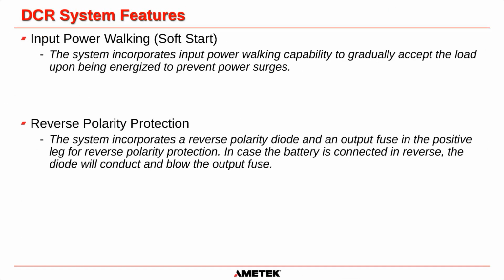Some features of our DCR system. We have input power walking, so we slowly, gradually ramp up the DC voltage and current to accept the load and prevent power surges. And we have reverse polarity protection to prevent the positive or negative legs of the output from being reversed. If it is reversed, it'll blow an input fuse, or an output fuse, I'm sorry.